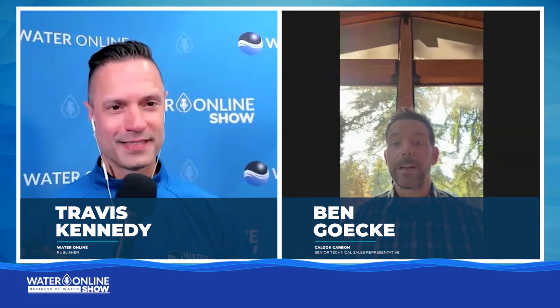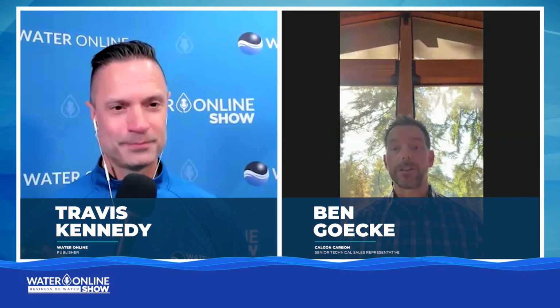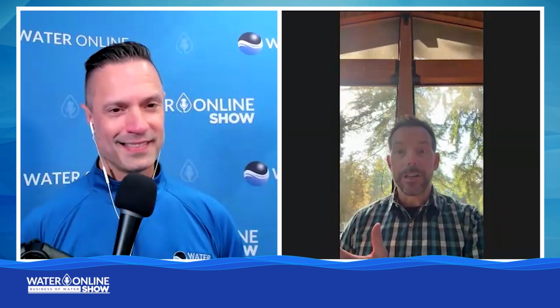Yeah. Well, just to talk you through the process a little bit, when the media is spent and you've got to change it out, we bring out a trailer. These trailers have multiple compartments, so we hook up one of the empty compartments to the vessel. The vessel's usually already full of water. We pressurize it, and then we open the valves, and the media just slurries into the truck.